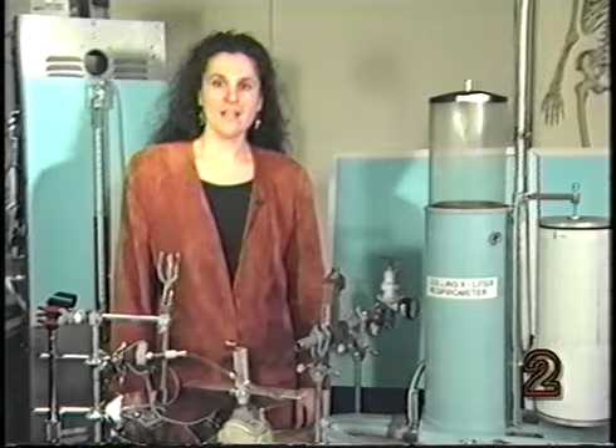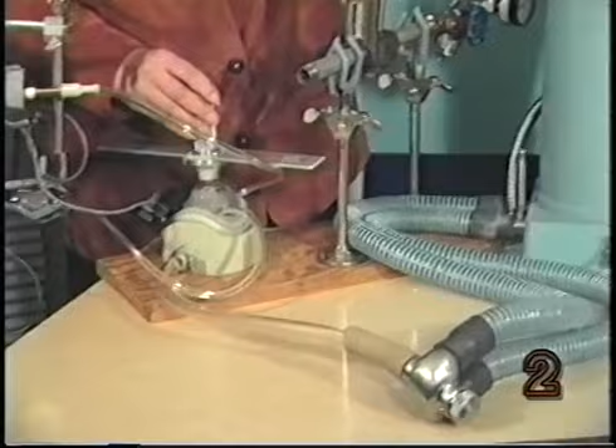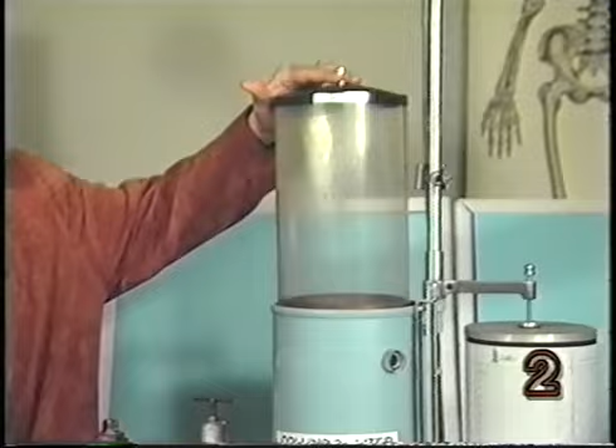Our next calibration procedure is for making the volume measurements. By not having our subjects breathe into a respirometer to calibrate for volume, we don't fatigue them with an additional calibration maneuver. This has been especially helpful when working with the children or with hard-to-test patients. This time we connect the mask on the mold to the respirometer, and we repeatedly displace 2 liters of air through the mask. We digitally integrate this cyclic flow signal and then scale our low-frequency flow channel. This allows us to calculate the volume displacement by integrating the flow signal.